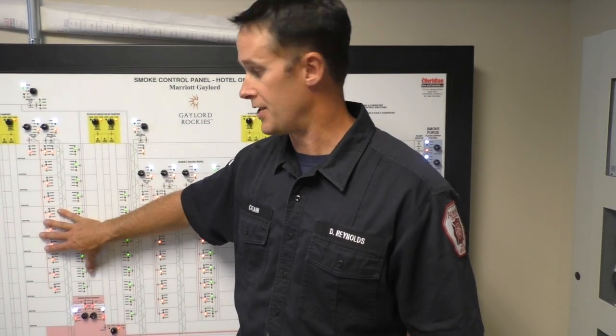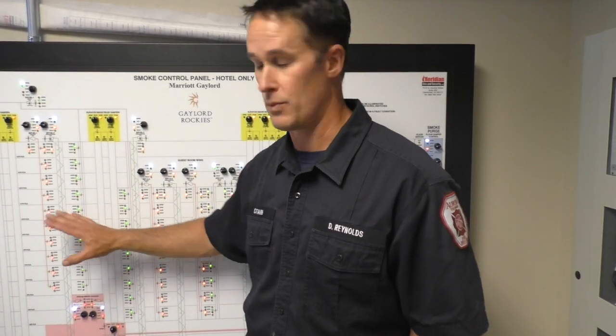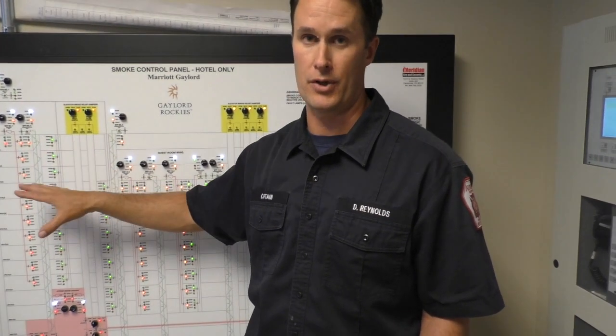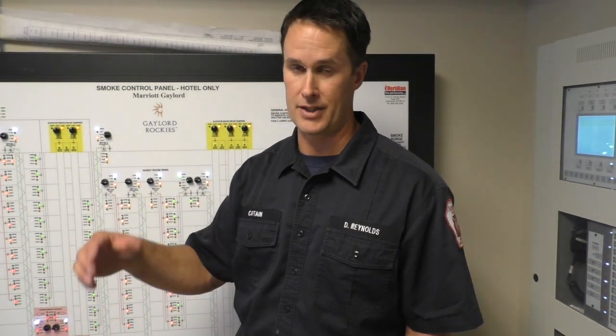Once we've controlled everything and we've got whatever we need shut down, then we want to make sure that we pressurize our stairwells. Then we can start thinking about pressurizing other floors, making sure that we don't create a flow path. And once the fire's under control, we've got a majority of the fire knocked down, then we can start thinking about using the system to exhaust smoke on multiple floors. We don't want to do that until we know they've got control of the fire, because then we open up a flow path and we can create more trouble.